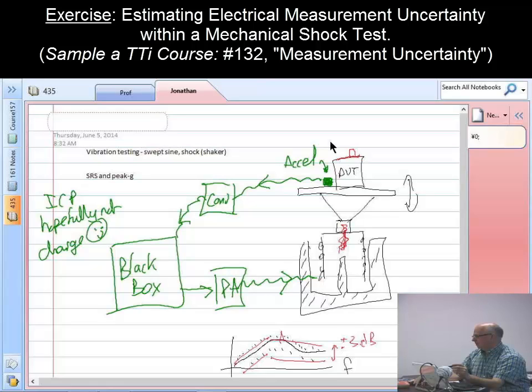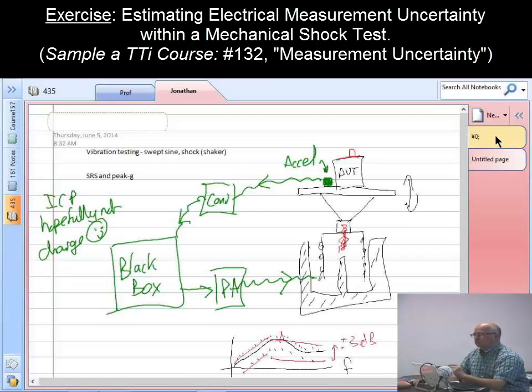But my question came about where a lot of times, we're running these tests, and in a few instances, people will come and ask about the measurement uncertainty involved with the data. I've seen different sets of calculations on how this can be calculated, but I've never seen anything consistent about it. So I guess the simplest would be to break down each component in series, maybe first with that simple setup of the accel cable going into the signal conditioner, and then that going into the black box, which could serve as the vibration control system / data acquisition system.